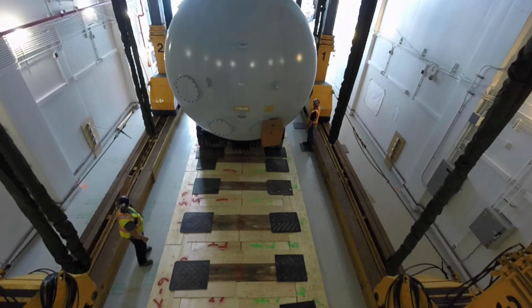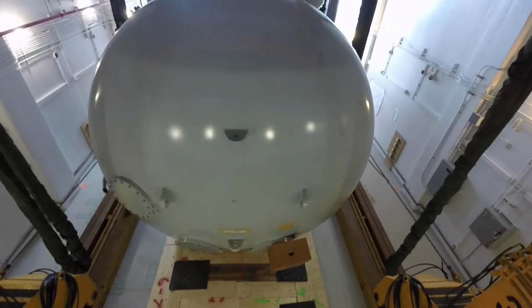The other challenging aspect here is the use of two tandem cranes: a 550-ton and a 650-ton tandem crane with separate operators, operating a ballet of chasing and dropping this 155-ton transformer tank into the station. It went through an opening in the roof with about 18 inches to spare, a very exciting activity. Overall, the entire delivery event took 2.5 days, with a 2.5-day road closure to ensure that could happen. With that, I am complete.